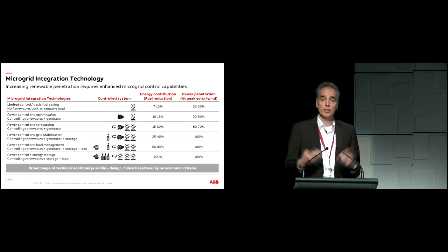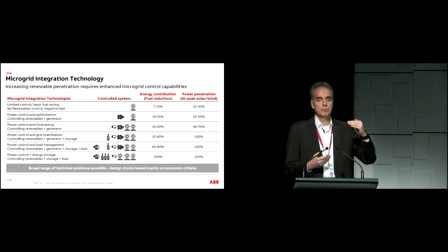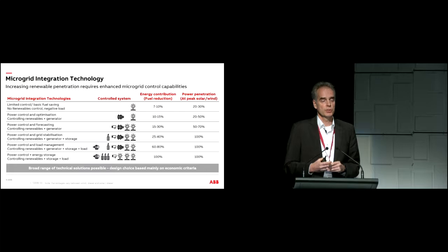Next is to look at technology that's available around, for instance, cloud forecasting. So cameras that look at cloud prediction really help us to ramp down the PV before the clouds hit, and therefore avoid this step load in the generator that might have to pick up the loss of the PV, making a much smoother transition. But again, it's only getting us to maybe 15 or 30% in order to offset more fuel.